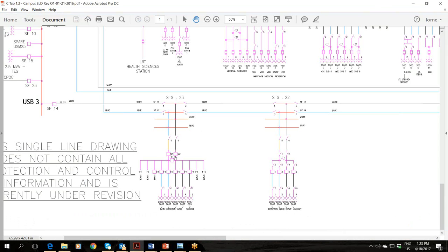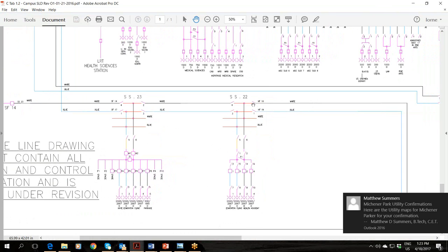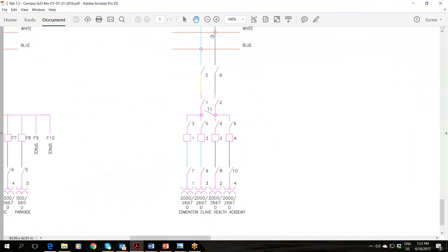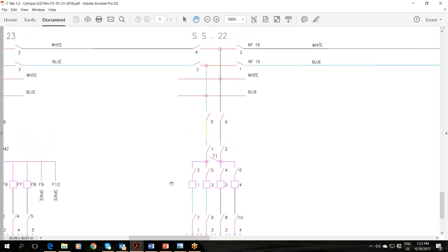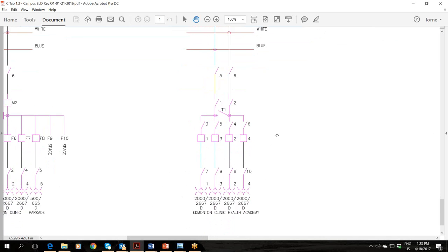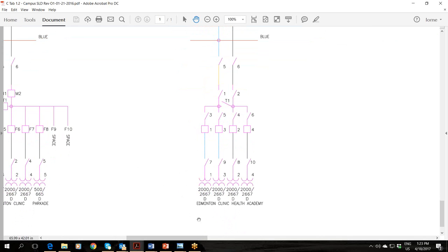So I'm going to flip back to the main single line. I just want to dive down a little further now into our system, into a building. We're going to focus on this sectionalizer here, and then the supply out of this sectionalizer goes down into one of our buildings, which happens to be the Edmonton Clinic Health Academy, one of the newer buildings on campus. We've changed the way we do distribution a little bit. In the past, these would all be fused disconnects. So we're moving to a fixed mounted 15 kV breaker with a protective relay. That gives us an opportunity to do differential protection across the transformer and have better overall protection, lower arc flash, those types of things.